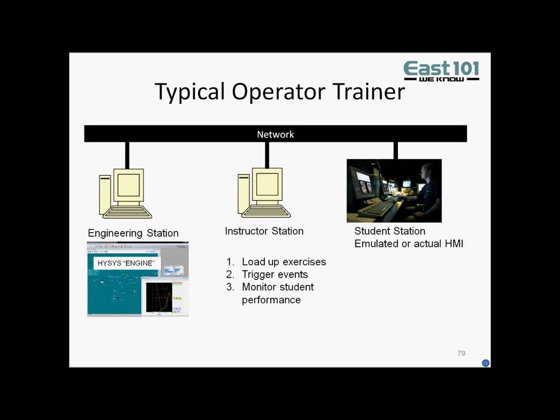Here is a representation of a typical operator trainer. At its core is the engineering station, which could be one or many machines, depending on the complexity of the solution required. The engineering station is responsible for running the dynamic solver — it could be HYSYS, UNISIM, or any simulation software. The relevant values being calculated will be visible from designated instructor and student stations. The instructor stations will have the ability to select exercises, trigger events, and monitor the student's performance. The student station, however, is only allowed to respond to the events being simulated.